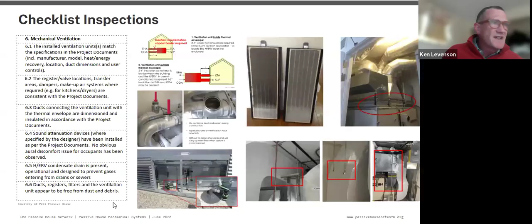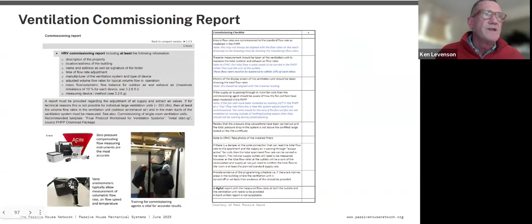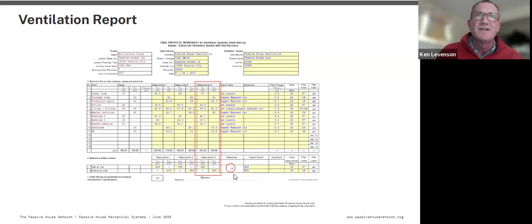There is a more extensive checklist - there's a report for the balancing in the commissioning report. I'm not going to go into all of this, but we are measuring all the supplies and exhausts, and we need that report showing that we're hitting the numbers. At the unit, at the fresh air and exhaust, we are measuring those volumes, and here we see it within 1% of each other, which is fabulous - that's what we want to see. So this kind of report is being issued.